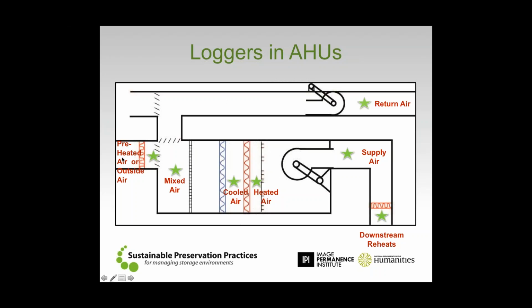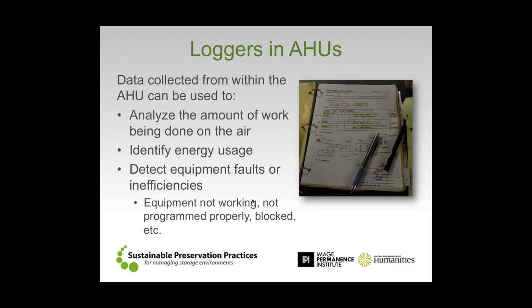And we're going from the return air, maybe we have outside air over here, a preheating coil. What might that mixed air condition be between the return air and that outside air stream? How much work does the cooling coil do, and how much work does the heating coil do? And as we start to pull all of that data over time and gather it in and bring it up on a graph or start to run through the analysis portion of it, not only can we find just how much work is being done, if we look at a mixed air condition and then look at the cooled air condition, we can figure out exactly how many degrees of cooling that cooling coil is actually doing, both sensible and latent, both in terms of sensible temperature and dehumidification.